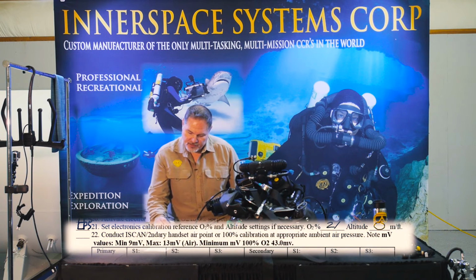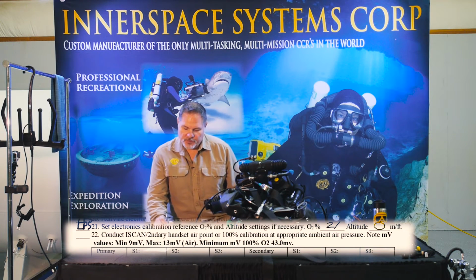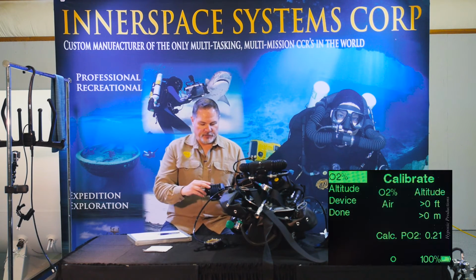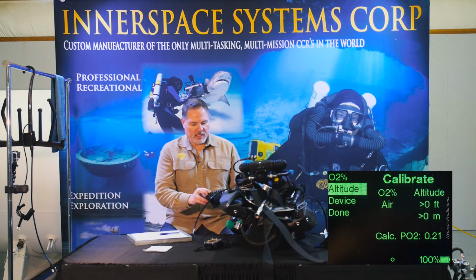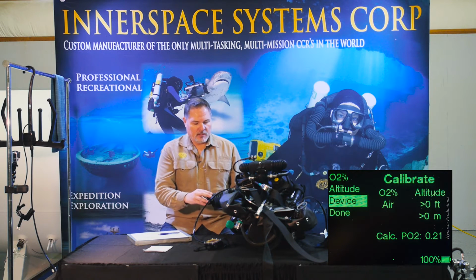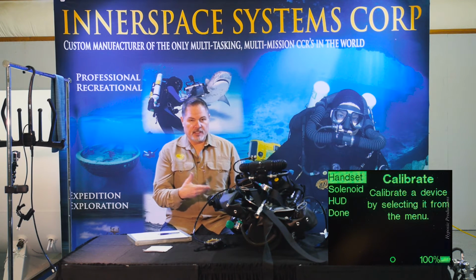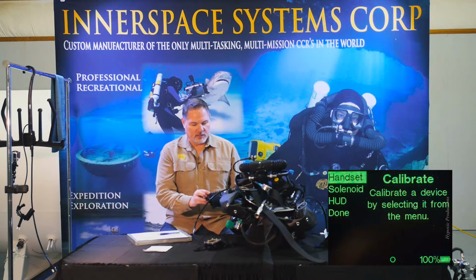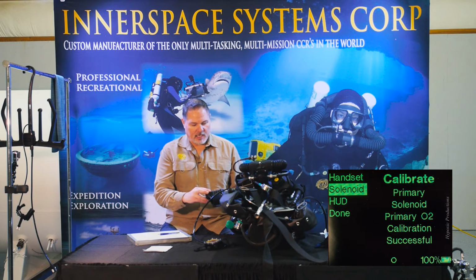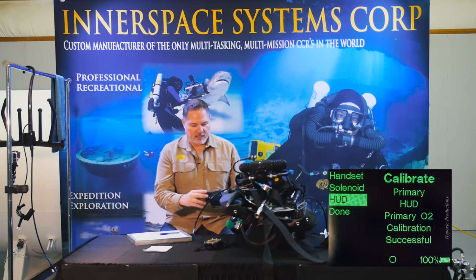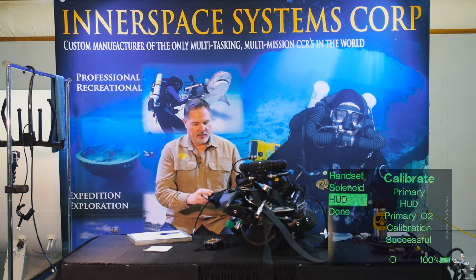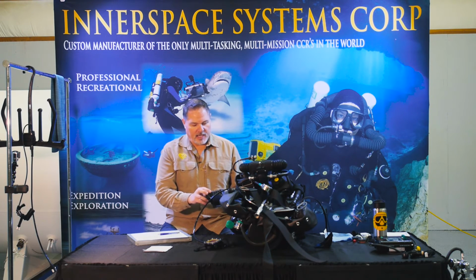Conduct an ISCAN and secondary handset air point, or 100% calibration if appropriate, at ambient air pressure. Note the millivolt values. So I go to device, and I see handset, solenoid, and HUD. Remember, this is in calibrate mode. Calibrate handset, calibrate the solenoid, calibrate the HUD. I'm done with calibration, and I'm going to get out of that.